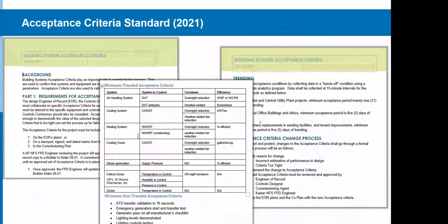In 2021, we revised that acceptance criteria standard. So now we're very specific about what the design engineer and the commissioning team have to put together in acceptance criteria. There's also an acceptance criteria change process. What we've seen happen a lot is that during design, a team will establish acceptance criteria, and then you get to commissioning and wildly fail that acceptance criteria.